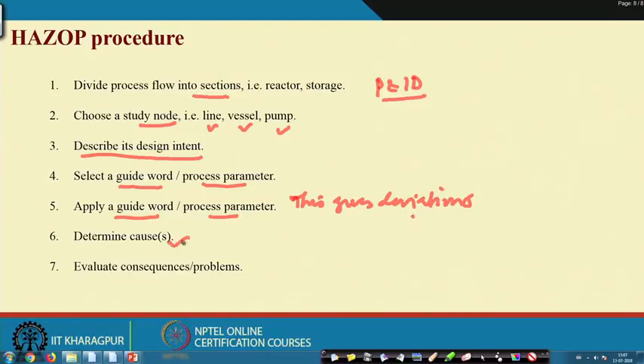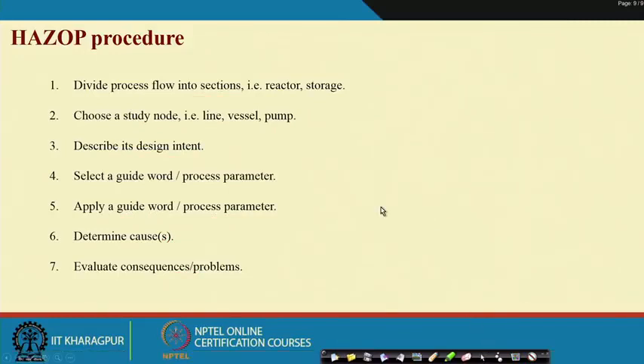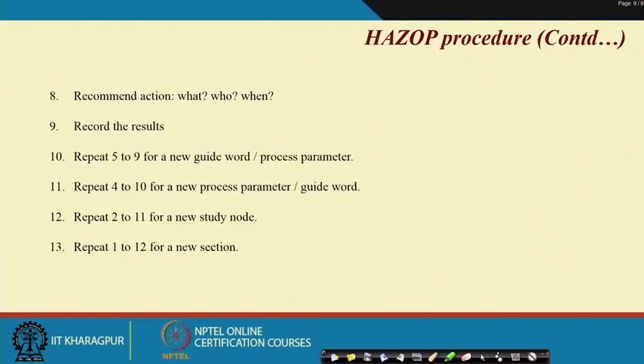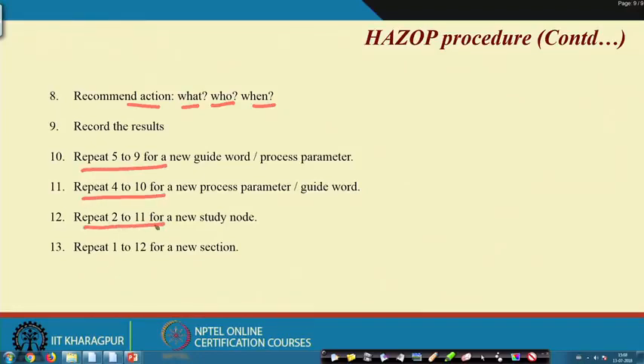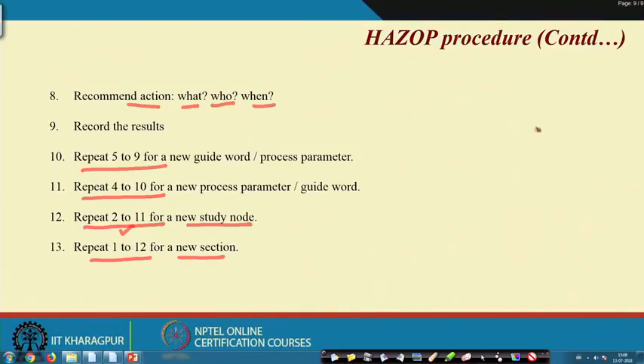Then repeat: you write down some action - what to do, who will do it, and when it will be done. Your results will be documented. Repeat steps 5 to 9 for every new guide word; repeat steps 4 to 10 for every process parameter; repeat steps 2 to 11 for a new study node; and repeat steps 1 to 12 for a new section.